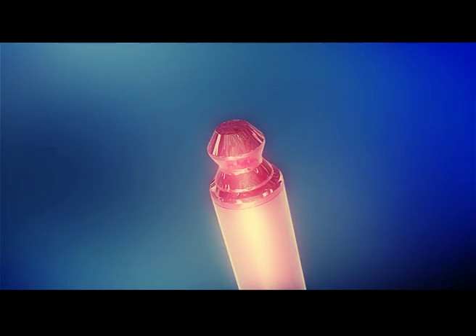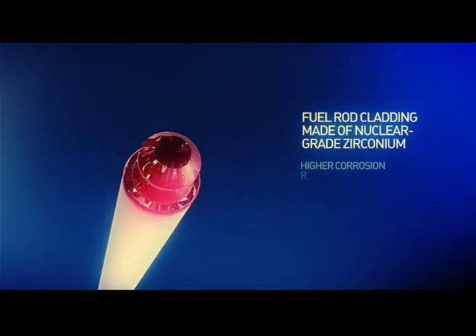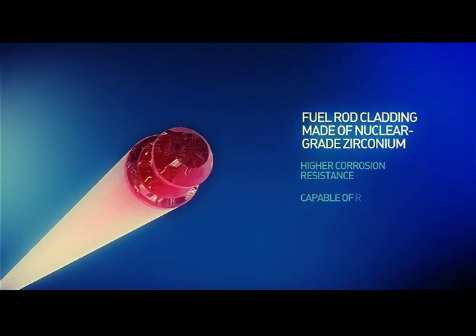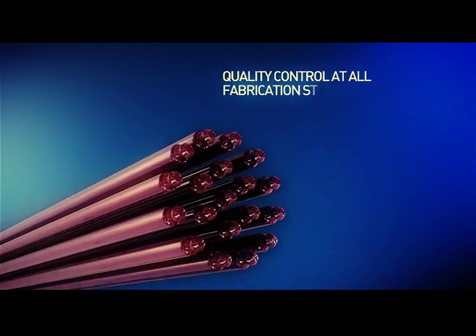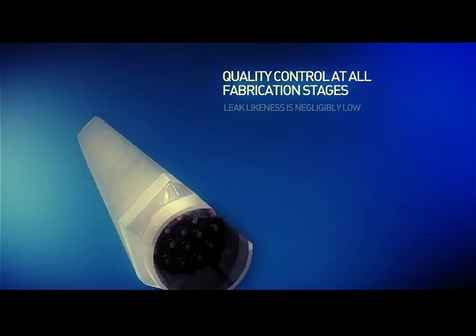Leak-tightness of the fuel rod zirconium cladding is the second safety barrier. The fuel rod cladding is made of nuclear-grade zirconium and possesses higher corrosion resistance. It is capable of retaining its shape under temperatures of more than 1,000 degrees Celsius. Quality control over nuclear fabrication is exercised at all process stages. Multiple quality checks make probability of fuel leaks negligibly low.